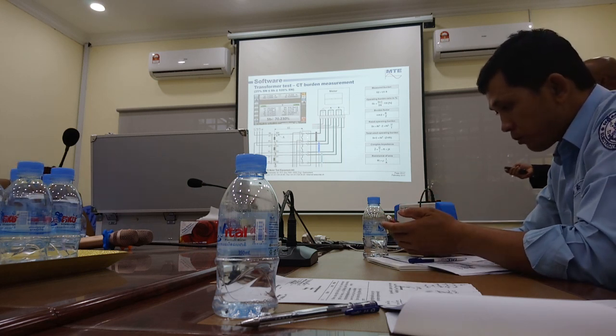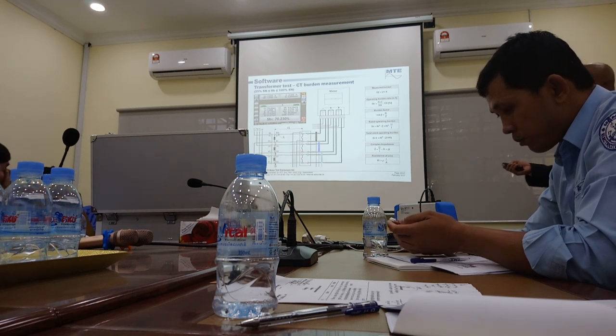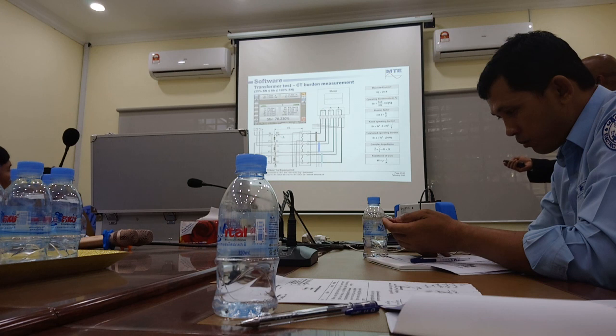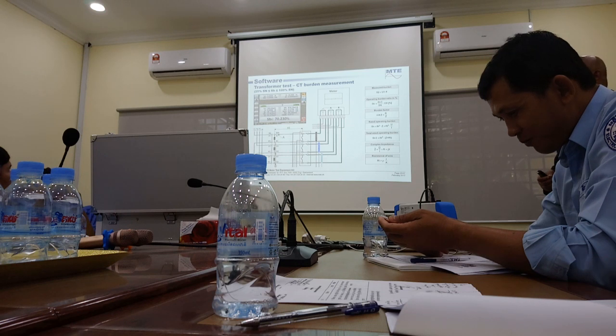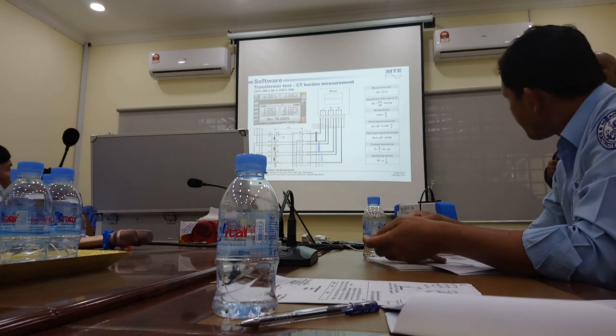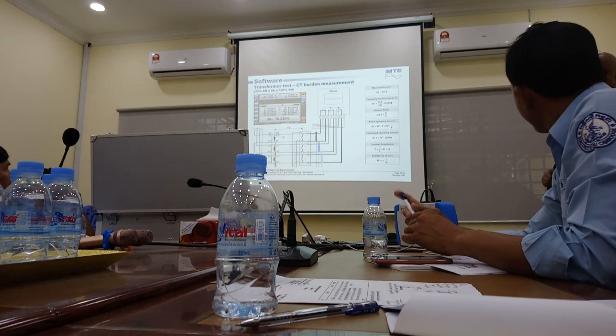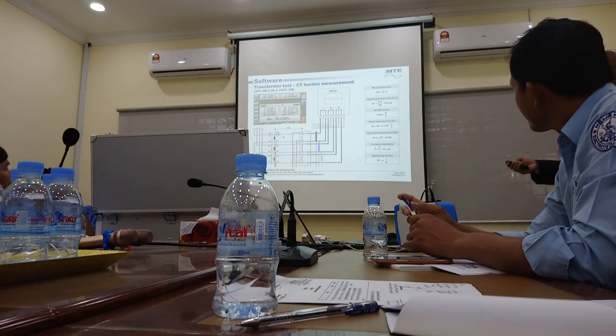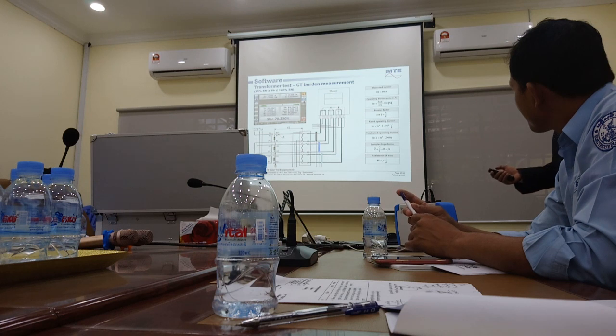So this is very simple. Okay, for CT measurement it is a bit tricky because how do you measure CT? You basically pass the current through the current terminal of the meter and measure the voltage across that. Okay, so it is basically your resistance of the wire most of the time. Why is this very tricky? Because you go to the customer and may not have enough load at that time. So it is very difficult to do this test in the field when the customer load is too small.